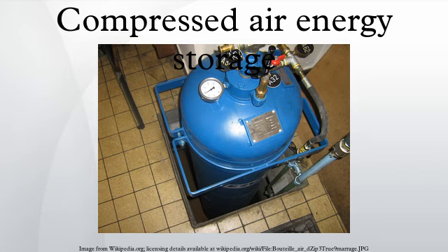The theoretical efficiency of the adiabatic storage approach is 100% with perfect insulation, but in practice round-trip efficiency is expected to be 70%. Heat can be stored in a solid such as concrete or stone, or more likely in a fluid such as hot oil or molten salt solutions.